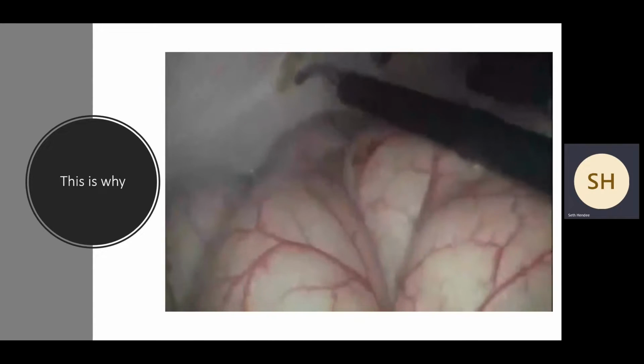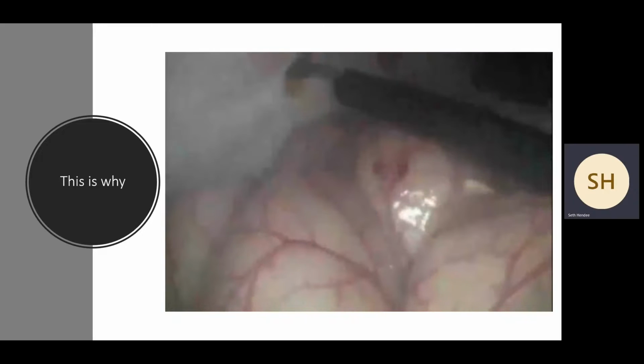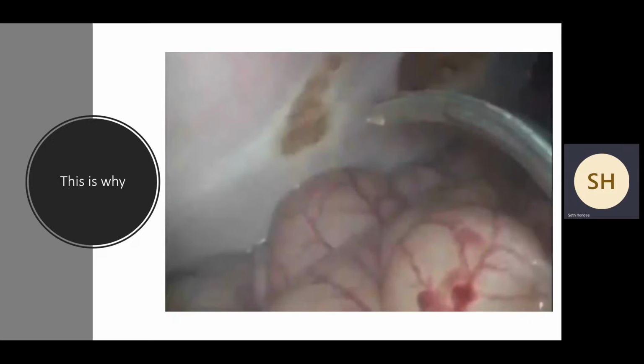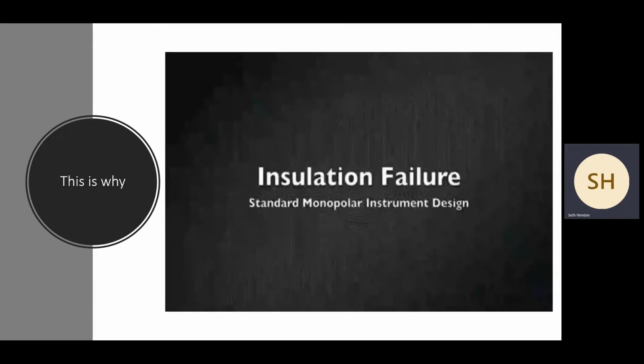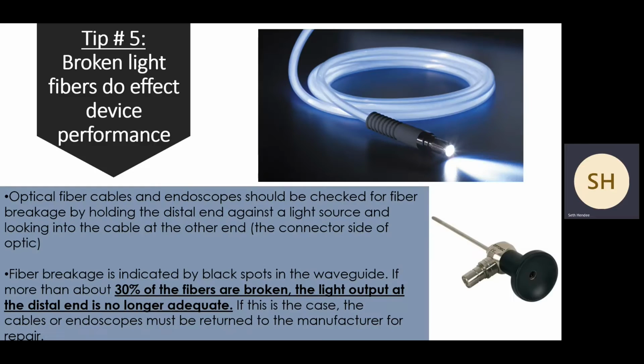You see that unintended tissue burn right there? This is the problem. And the worst part is only because there was a camera pulling back from that shot did we get to see it. Okay. You want the surgical team, you want the surgeon looking right at the point of cauterization. So they're usually just looking at the very, very tip of that instrument, which they should. That's the only place that burning and clipping and cutting should be happening. So that's where we want them to look.